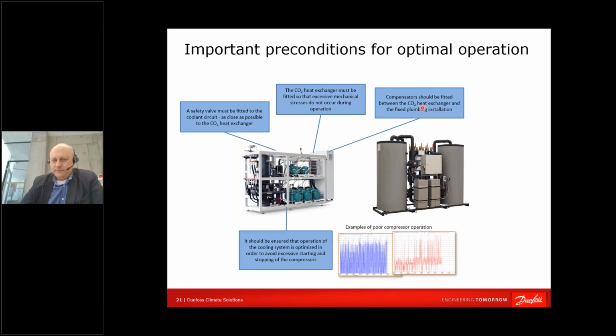Compensators should be fitted between the CO2 heat exchanger and the fixed plumbing pipe, because the cooling rack is vibrating because of the work of the compressors. So the pipe, which is welded or soldered to the heat exchanger, will be stressed every time. Of course, it would be nice to eliminate vibrations. A safety valve should be on the water side, just to open on sudden temperature increases.